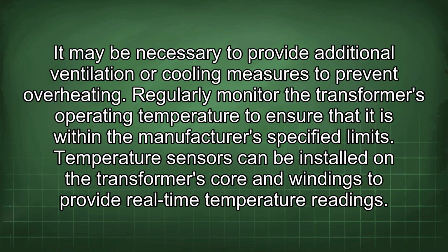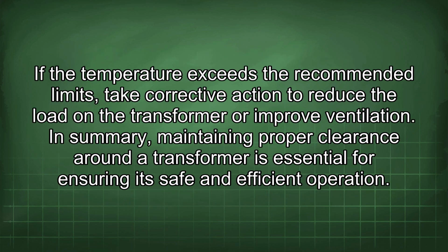Regularly monitor the transformer's operating temperature to ensure that it is within the manufacturer's specified limits. Temperature sensors can be installed on the transformer's core and windings to provide real-time temperature readings. If the temperature exceeds the recommended limits, take corrective action to reduce the load on the transformer or improve ventilation.